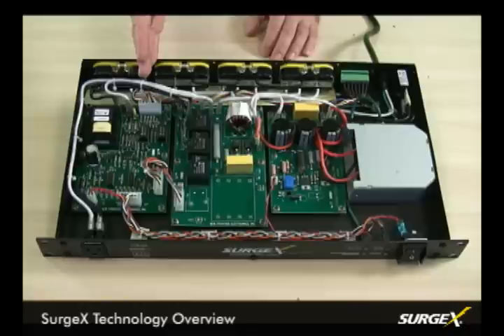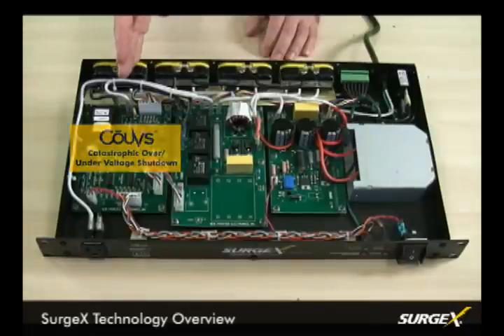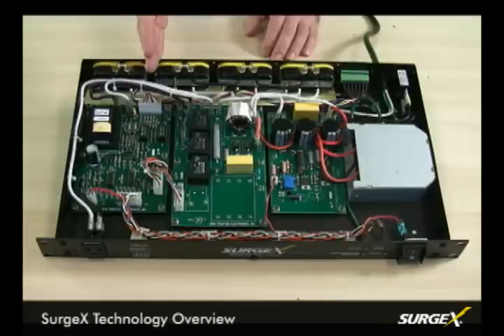This unit also has our COUVS technology, which is our catastrophic over/under voltage shutdown, and that protects you from sustained over voltage and under voltage situations. This technology will disconnect the load when the voltage drops to 90 volts, or if the voltage is raised and sustained at 145 volts. With our COUVS technology, this unit will actually reset itself once the line voltage has returned to a safe and stable level.